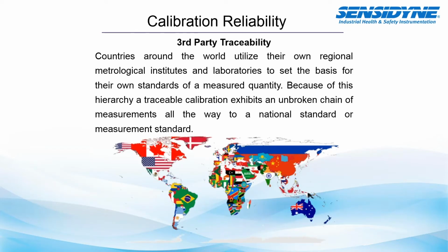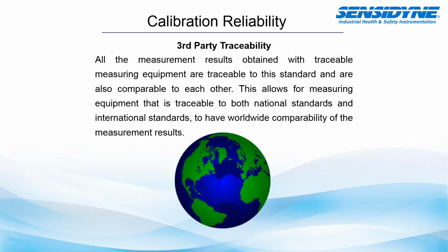Now, countries around the world will utilize their own regional metrological institutes and laboratories to set the basis for their own standards. Because of this hierarchy, though, the traceability calibration exhibits an unbroken chain. Basically, this means that a unit of measurement in Brazil should mean the same unit of measurement in England, Australia, and the United States. All the measurements obtained with traceable measurement equipment are traceable to this standard and will therefore be comparable to each other on a worldwide basis.